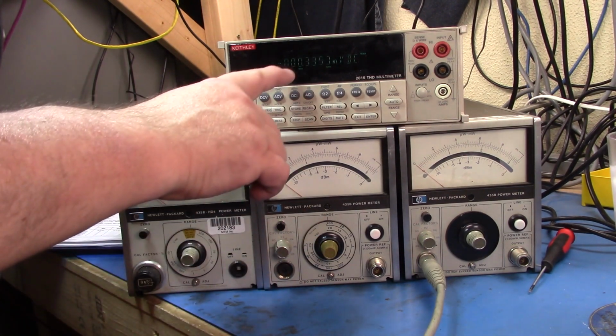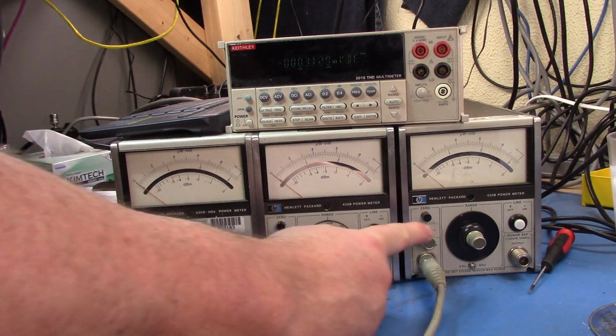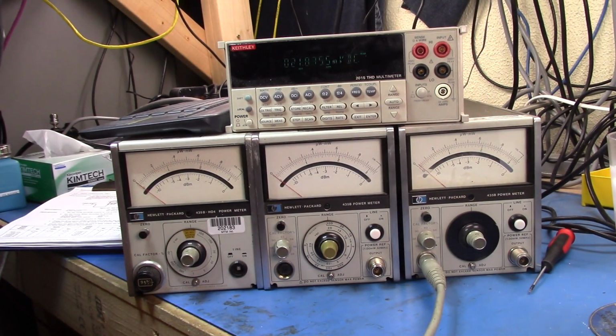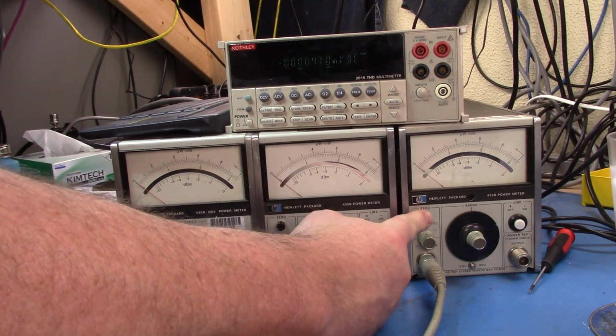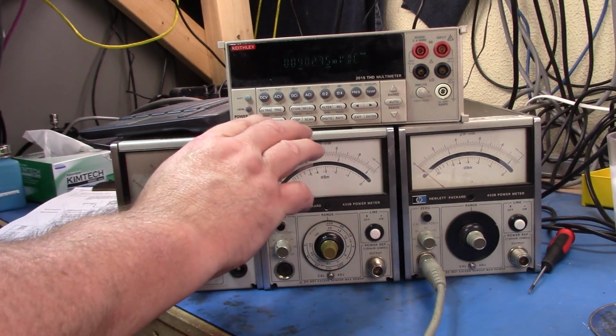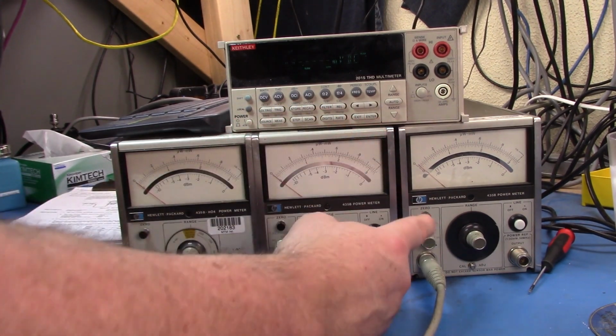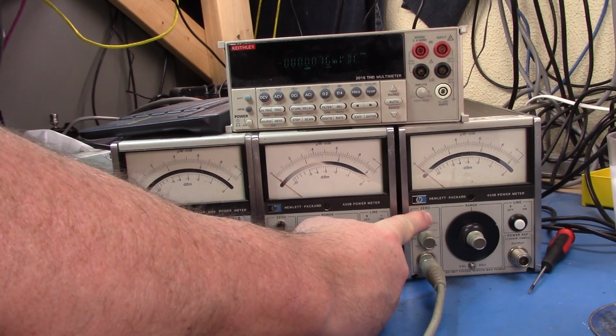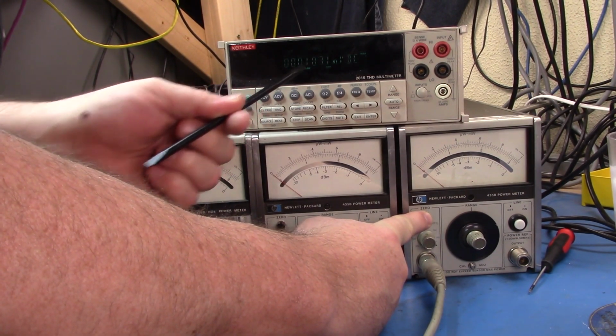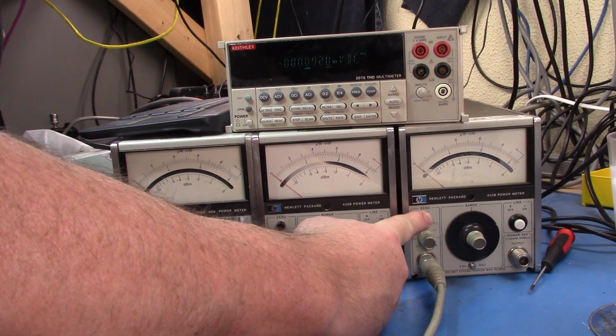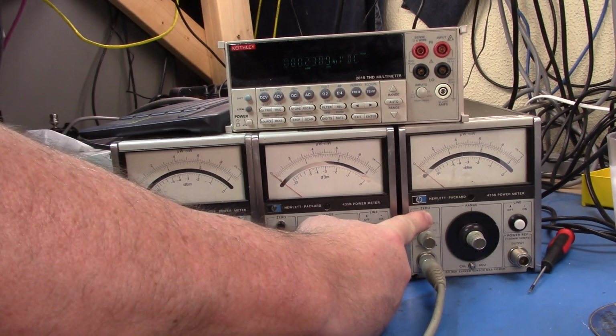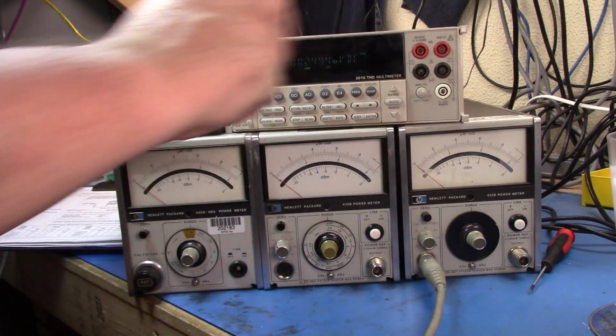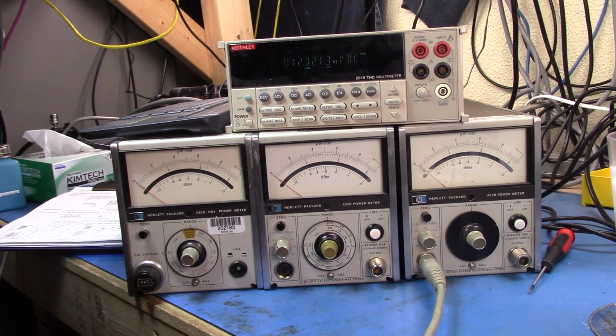So the first step is to check whether or not holding down the zero button on its most sensitive range will get us a meter reading of plus or minus 0.9 millivolt DC. So let's take a look at that. That's bouncing around way too much. So let's do, where's right. There we go. Let's turn that down to slow, and then we'll press this, and we get 0.1, 0.3, 0.1, 0.3, 0.2. Okay, so I think this is pretty much okay. So let's at least start the process.